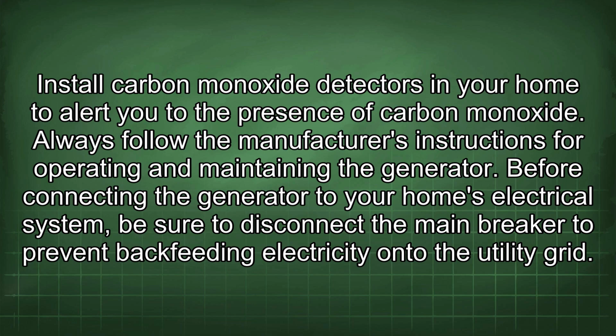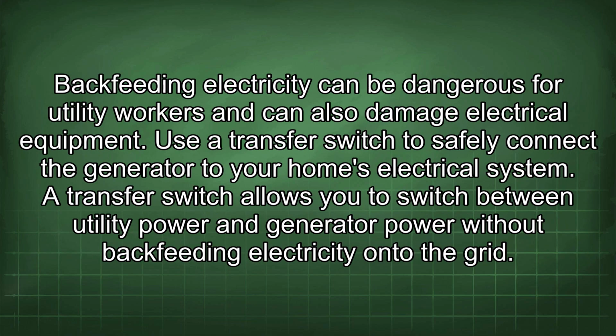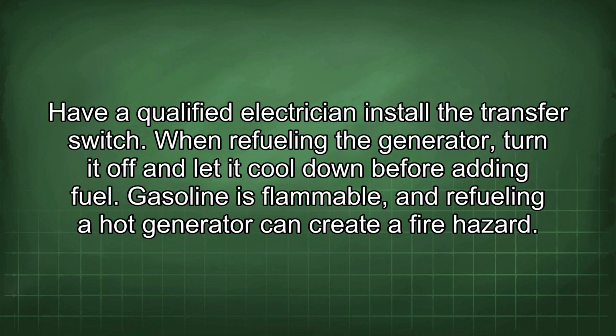Always follow the manufacturer's instructions for operating and maintaining the generator. Before connecting the generator to your home's electrical system, be sure to disconnect the main breaker to prevent backfeeding electricity onto the utility grid. Backfeeding electricity can be dangerous for utility workers and can also damage electrical equipment. Use a transfer switch to safely connect the generator to your home's electrical system. A transfer switch allows you to switch between utility power and generator power without backfeeding electricity onto the grid. Have a qualified electrician install the transfer switch.